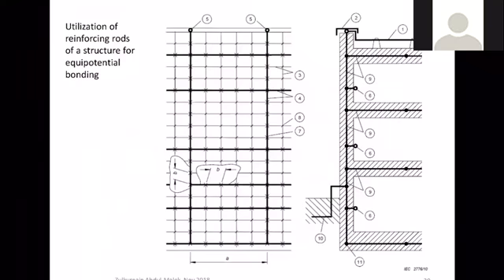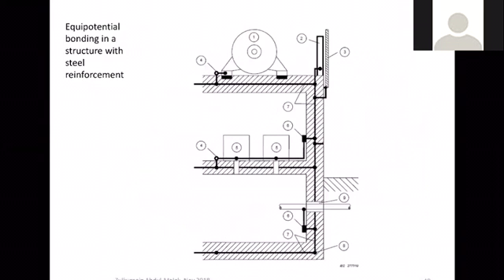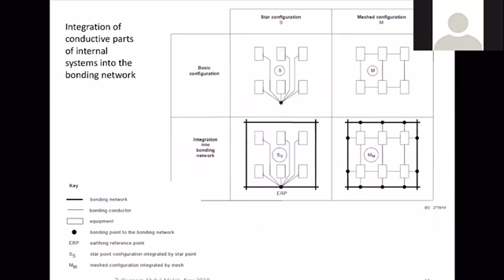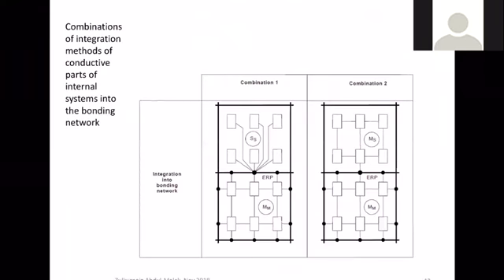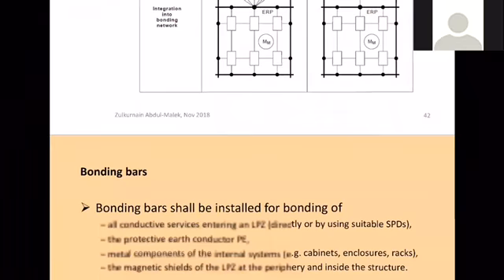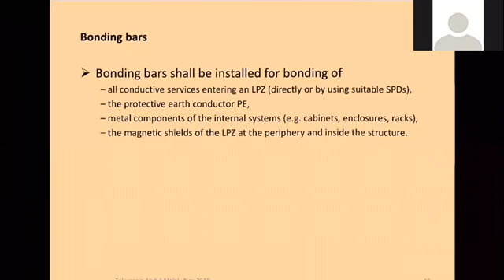These are methods of bonding. Here many layers need to be bonded together. Another method of bonding is the basic configuration, mesh or star configuration. Integration into the bonding network is shown here. The main physical things there are called bonding bars. The bonding bars are where all conductive services, gas, pipe, and so on, and power lines are connected, including SPDs. The protective earth is also connected here. Metal components of the internal system, cabinets, enclosures and racks are also connected to this bonding bar, as well as the magnetic shielding of the LPZ.